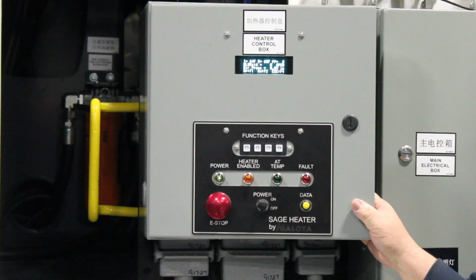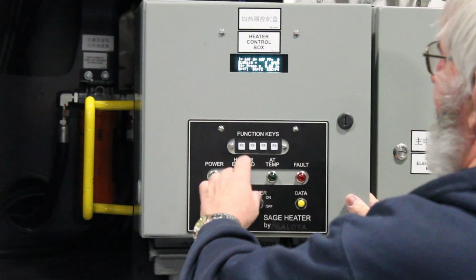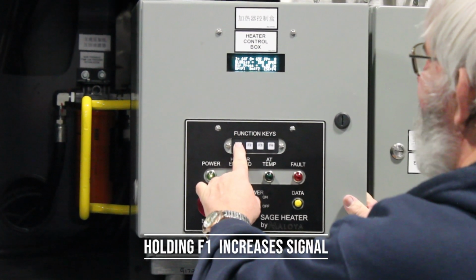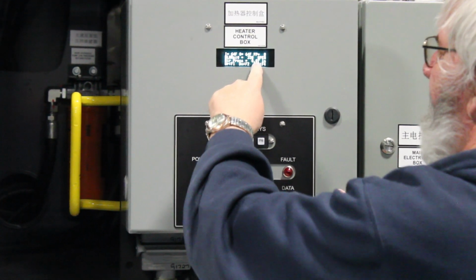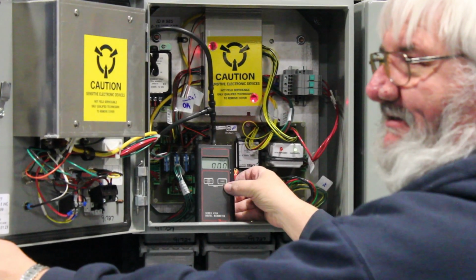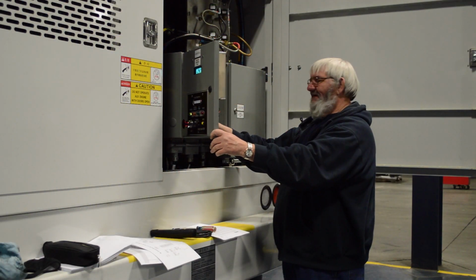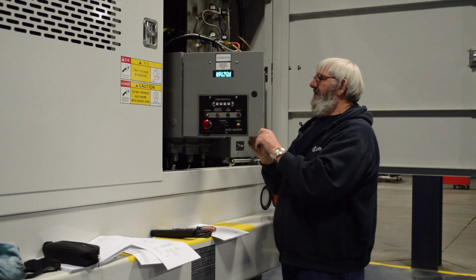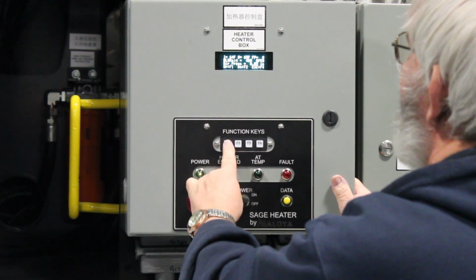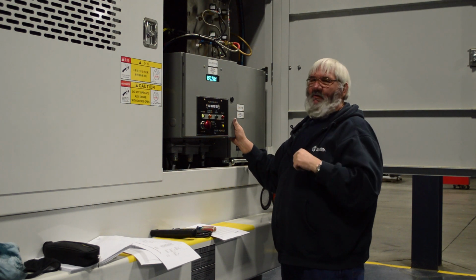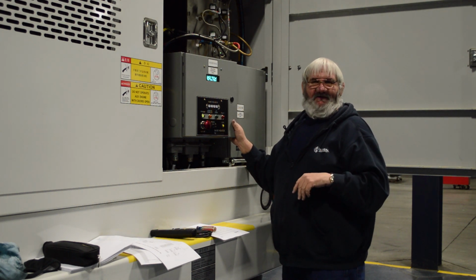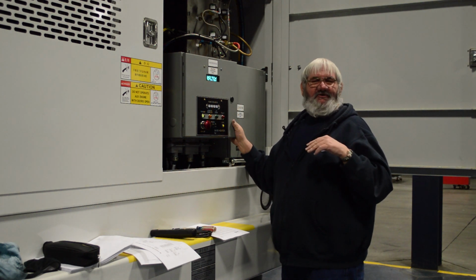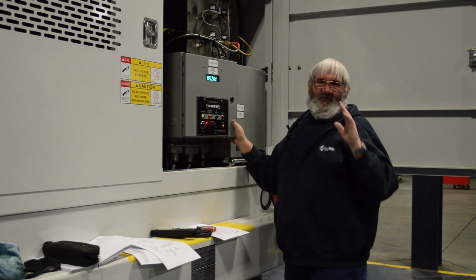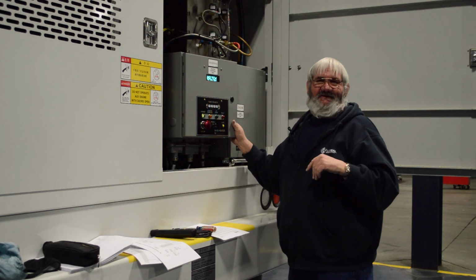In blower control test, here you would manually increase your signal. And as you increase your signal, you would see what your reading is on your air pressure transducer. And then you would compare that to the reading on your manometer. Now in a perfect world, they should be reading fairly close. If you continue scrolling up, typically I like to go from the bottom and work my way up, checking about 4 or 5 different points, making sure that the air pressure transducer reads through the complete range, that we don't have a dead spot someplace in the air pressure transducer readings.